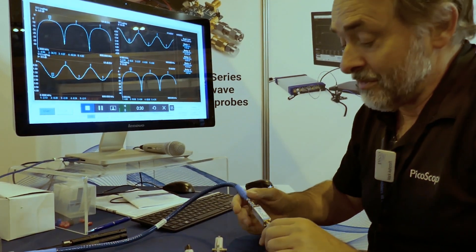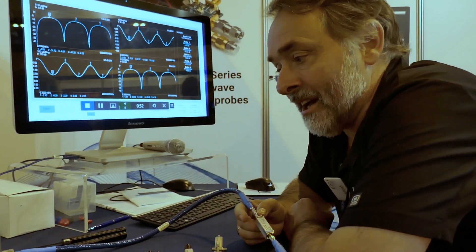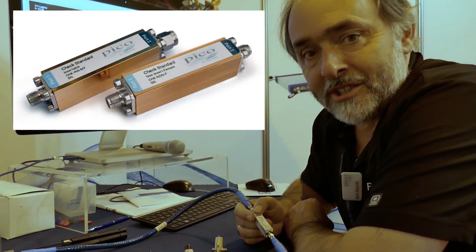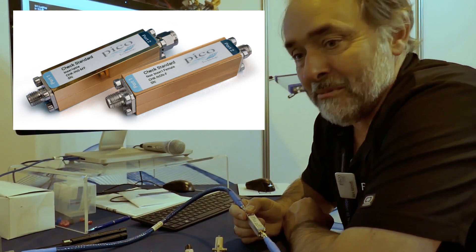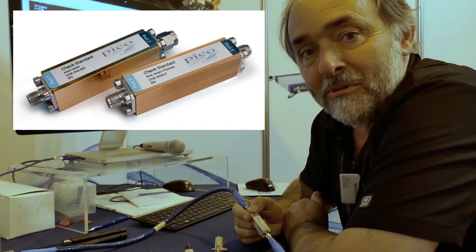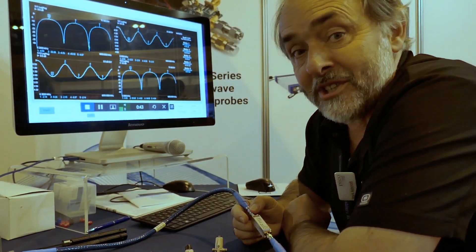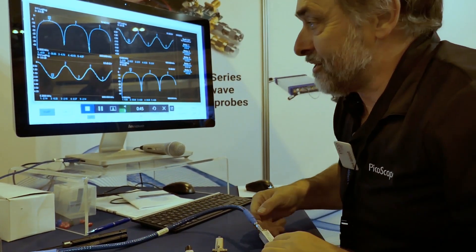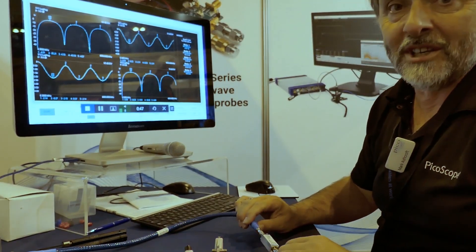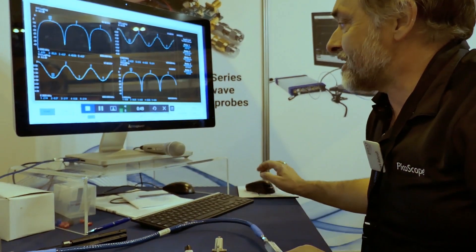One new product that I have with me is the check standard. We found that on our setup day we stumbled across a very good reason why you might want a check standard when you're making vector network analyzer measurements. On setup day we got everything up and running and we made our first measurements here of the check standard.